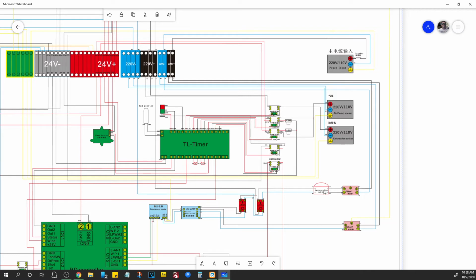Through filter 1, you go through the emergency stop. This is the important one that we're looking at if you're getting a no power issue right now and your machine won't come on. So it'll go through this EMI filter and then to the emergency stop, and that emergency stop is a double pole, single throw. So it will interrupt the line as well as the neutral. Now, if the emergency stop is correct and you have continuity here, if it's in the operating position, that power will go to the main power switch.